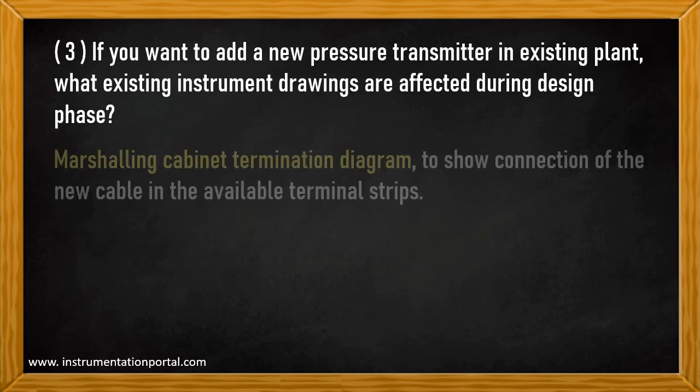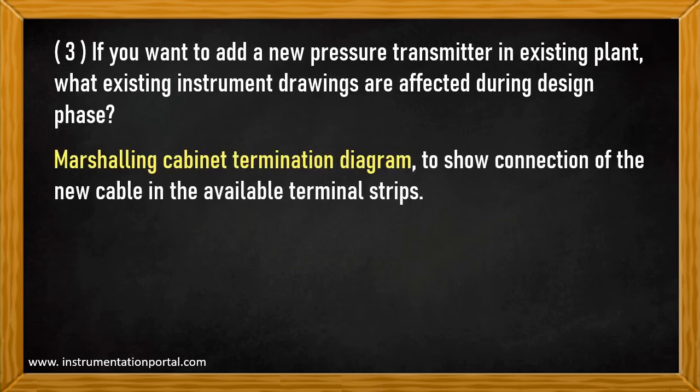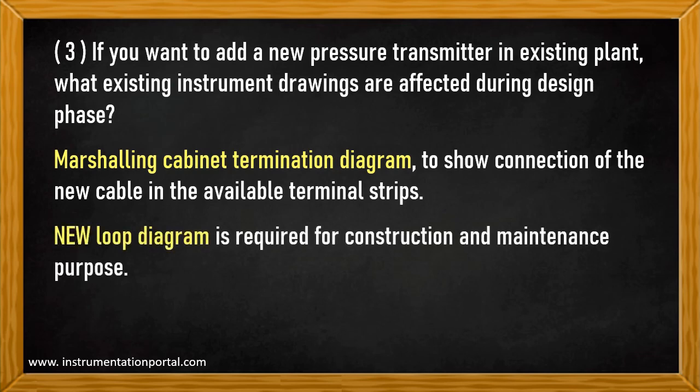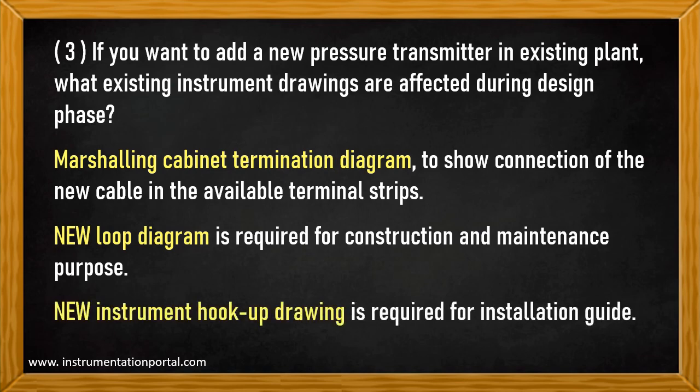The marshaling cabinet termination diagram must be updated to show the connection of the new cable in the available terminal strips. Besides updating existing drawings, new drawings must also be produced: a new loop diagram is required for construction and maintenance purposes, and a new instrument hookup drawing is required as an installation guide.